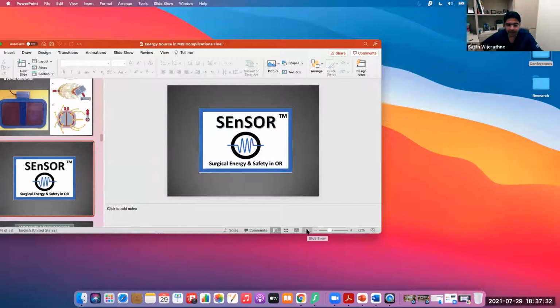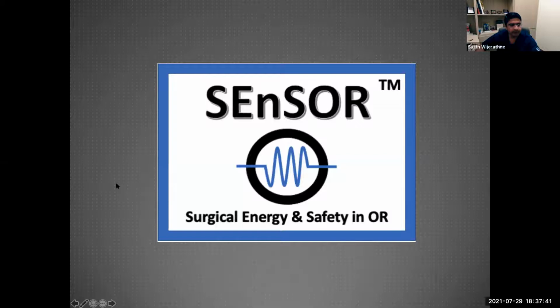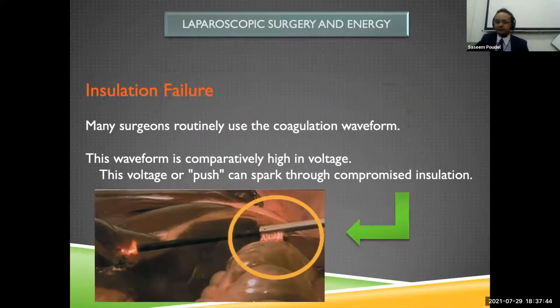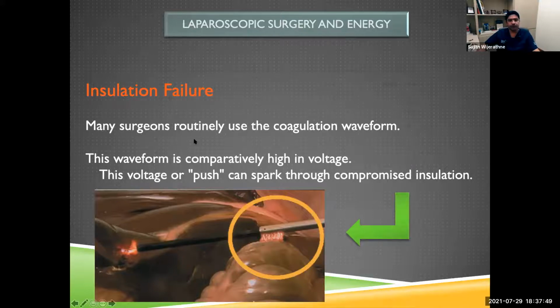Thanks, Sasi. We're going to have this as an interactive session because it's an important topic. So let's move to the next slide. Sasi, can you see my slide? Yes, I can see your slide. Okay. So insulation failure. This is an issue with current diversion. Many surgeons routinely use the coagulation waveform, and there are new machines available to check the insulation of our endoscopic electrosurgical instruments. But if these new machines are not available in certain places, you must look for the integrity of the insulation of your electrosurgical instruments.